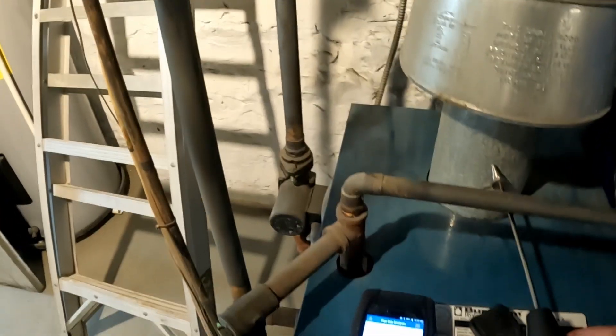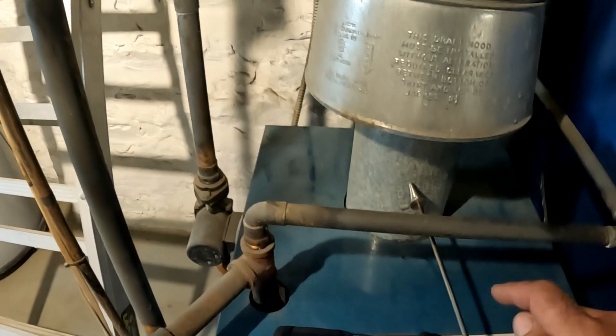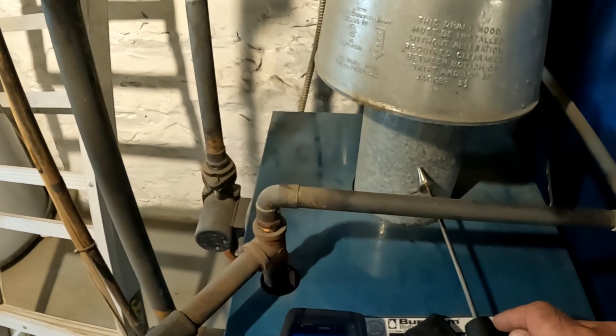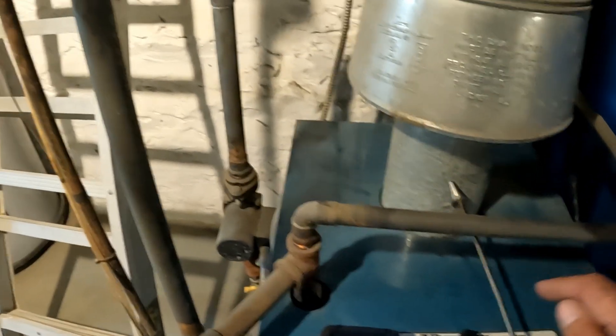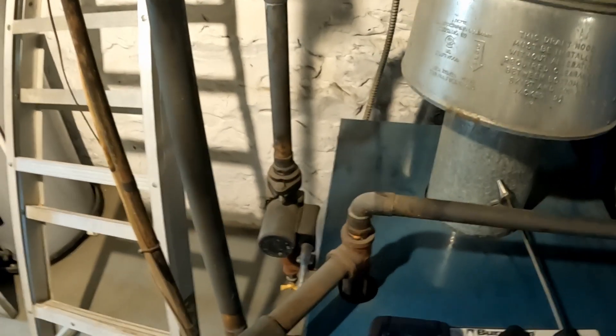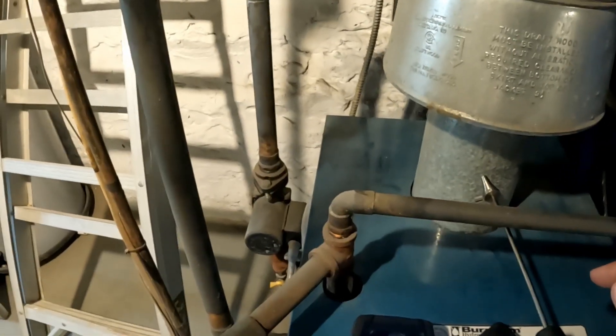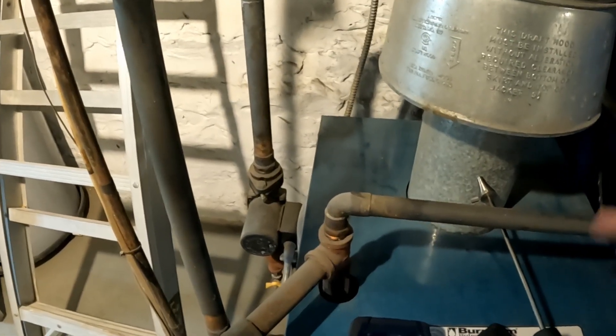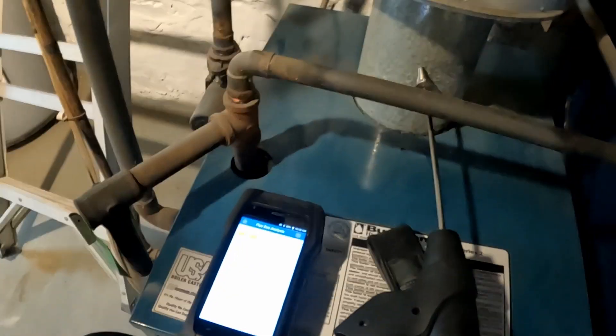Now, this is where we're going to start the combustion analysis and the draft test. The combustion analysis gets started before you take the heat in the boiler. It has to happen when the boiler starts. The startup shouldn't be more than 400 parts per million, give or take, of certain situations. You don't let the boiler heat up for five or ten minutes and take the analysis.